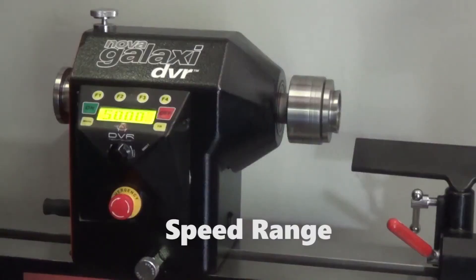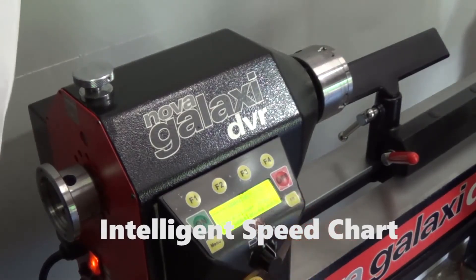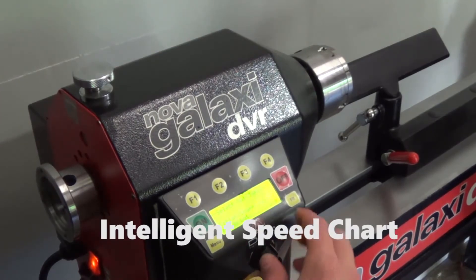The Galaxi provides the user with three built-in speed control profiles, each with slightly different PI controller coefficients and performance characteristics. These profiles are: soft, for work at speeds lower than 500 RPM; the default setting, normal, for most projects; and hard, for heavy or out-of-balance work at speeds lower than 500 RPM.